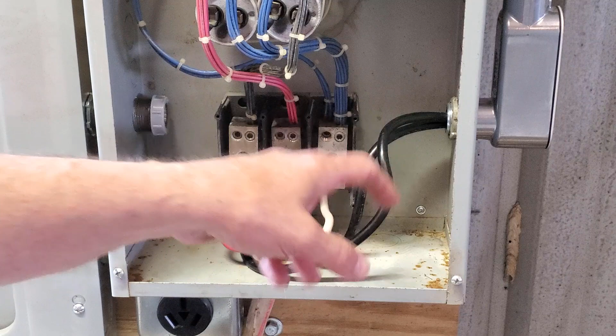23, 26, 38, 12, and 12. So here again we've got the source of the mystery current. We got 12 amps actual being supplied to the motor, but then 23, 26, 38 amps going to it. I know there's apparent power, and it has to do with power factor and power factor correction, I just don't fully understand it. There isn't extra free electrons coming through here, so somehow there's more current going back and forth in the leads to the motor than what's coming from the power company, but it is what it is. It runs.